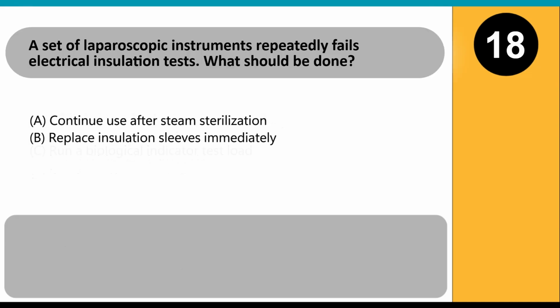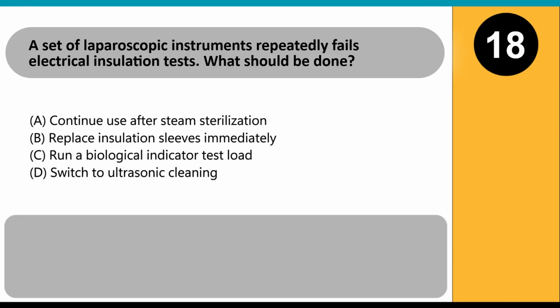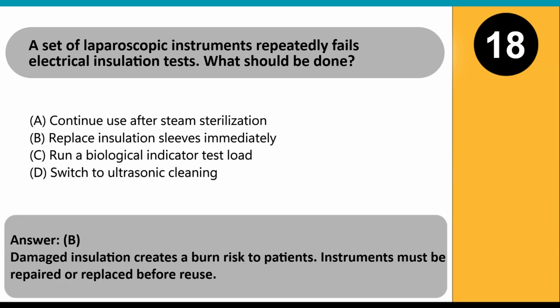A set of laparoscopic instruments repeatedly fails electrical insulation tests. What should be done? A. Continue use after steam sterilization. B. Replace insulation sleeves immediately. C. Run a biological indicator test load. D. Switch to ultrasonic cleaning. Answer: B. Damaged insulation creates a burn risk to patients. Instruments must be repaired or replaced before reuse.